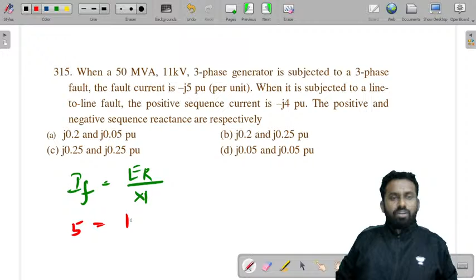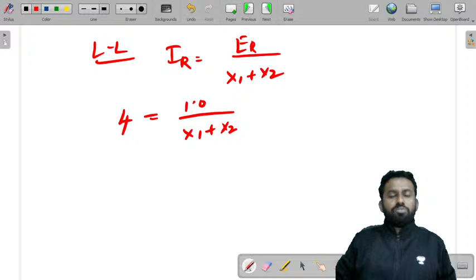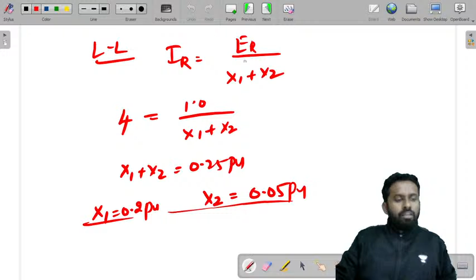Now let's find, for LL fault, IR is equal to ER by x1 plus x2. So this is 4. IR is equal to 1 by x1 plus x2. So what is x1 plus x2 value? We'll get it as 0.25 per unit. So x1 is 0.2 per unit, and x2 will be 0.05 per unit. So for an LL fault, the positive sequence current, and the positive sequence and negative sequence reactances are x1 is 0.2, x2 is 0.05. So this is A. The answer to this question is A.